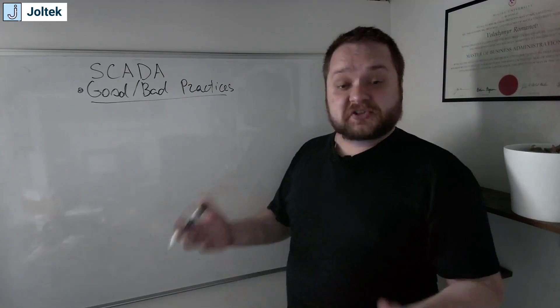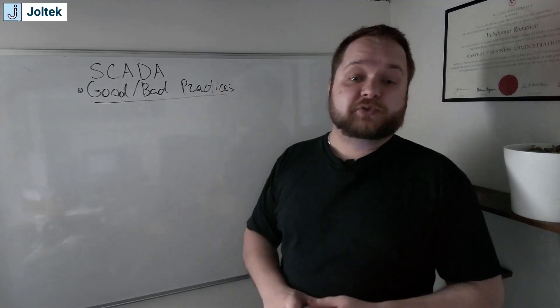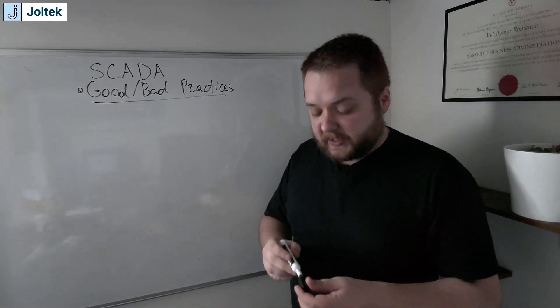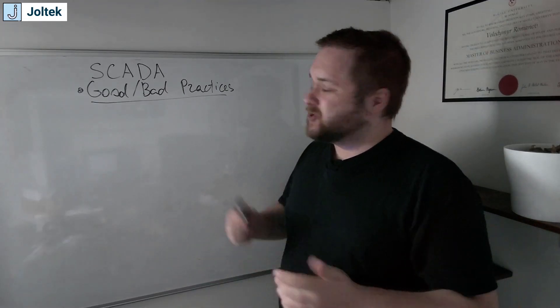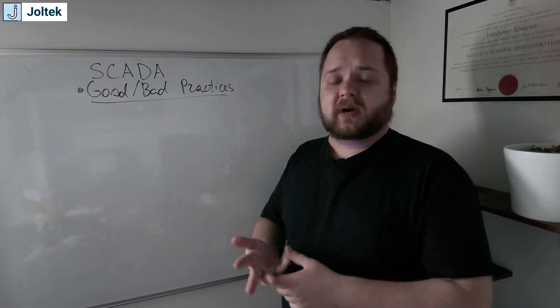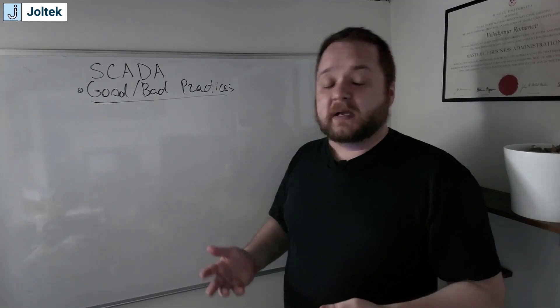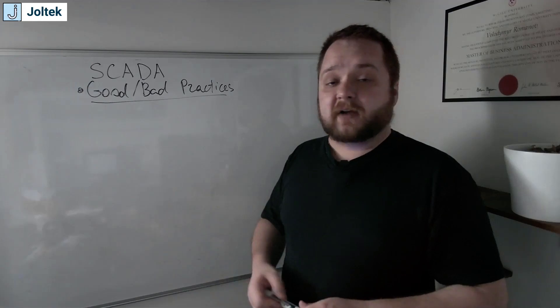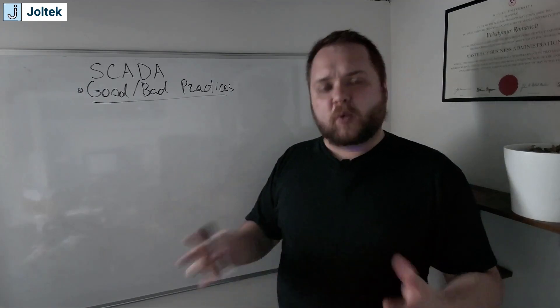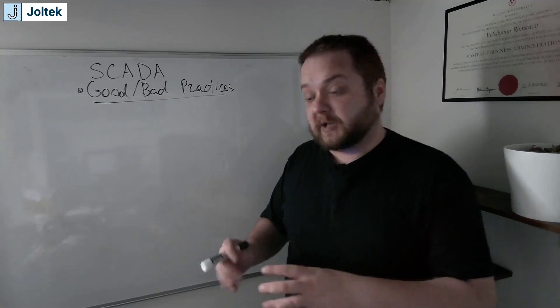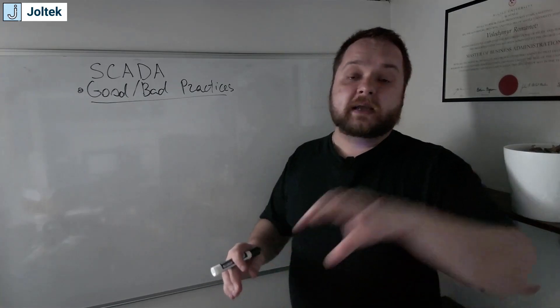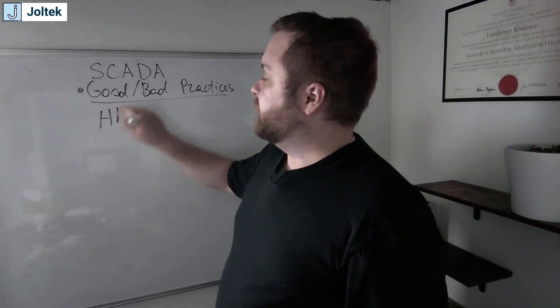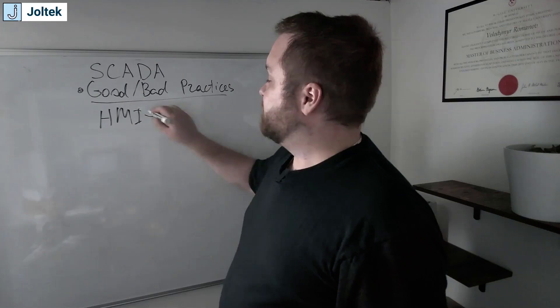So moving on to the next topic or discussion point of good and bad practices when it comes to SCADA. I've deployed my fair share of SCADA systems. I've troubleshot a lot of them. So I certainly have a lot of opinions when it comes to good and bad deployments. So I've already mentioned a couple of them in the conversation. But number one, picking an HMI and basically building it out to be a SCADA system is a recipe for disaster in terms of scaling. As your plant gets bigger, as you're trying to get more information out of that system, it becomes really difficult. There are ways to migrate. So if you're staying with the same manufacturer, a lot of times they will allow you to transition a standalone HMI into a SCADA type of a solution. But a lot of times, it is bad practice to build out an HMI into a SCADA. So I'm going to put that as a note. So an HMI is not equal to SCADA.